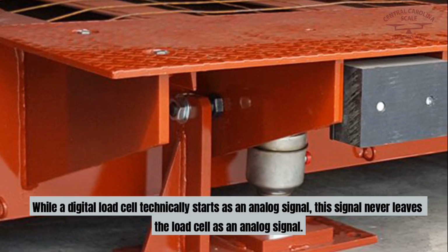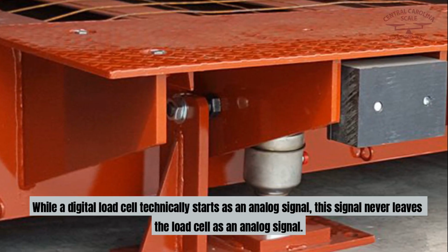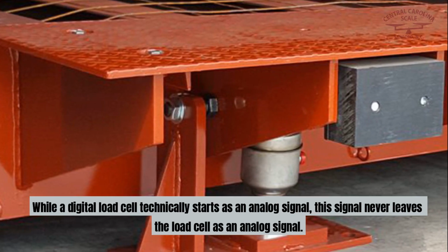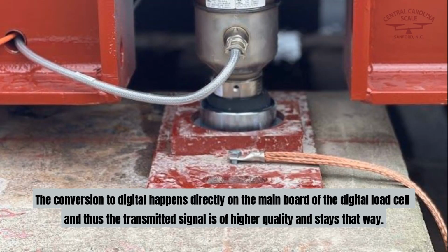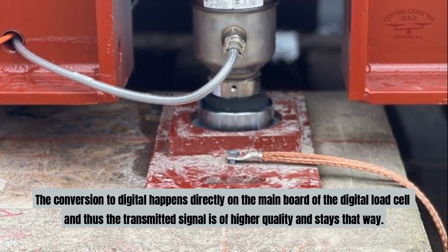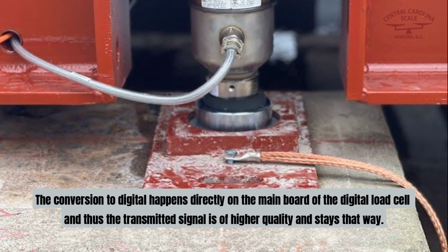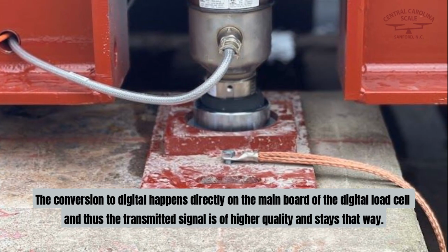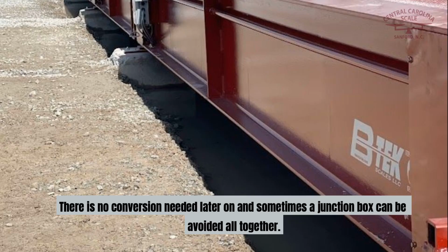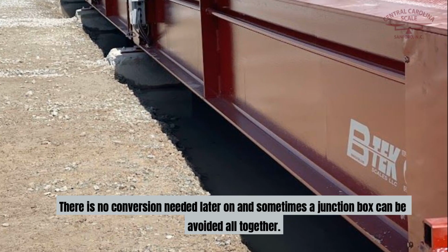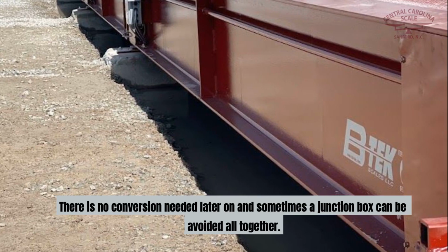While a digital load cell technically starts as an analog signal, this signal never leaves the load cell as an analog signal. The conversion to digital happens directly on the main board of the digital load cell, and thus the transmitted signal is of higher quality and stays that way. There is no conversion needed later on, and sometimes a junction box can be avoided altogether.